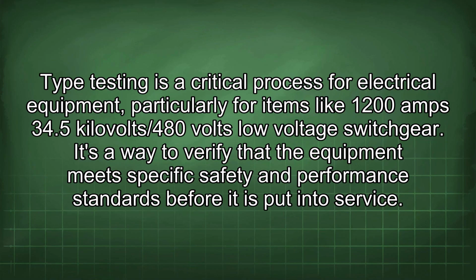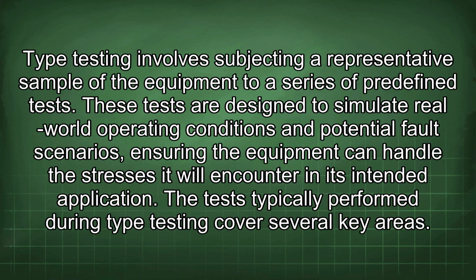Type testing is a critical process for electrical equipment, particularly for items like 1200 amps 34.5 kV/480 volts low voltage switchgear. It's a way to verify that the equipment meets specific safety and performance standards before it is put into service. Type testing involves subjecting a representative sample of the equipment to a series of predefined tests. These tests are designed to simulate real-world operating conditions and potential fault scenarios, ensuring the equipment can handle the stresses it will encounter in its intended application.